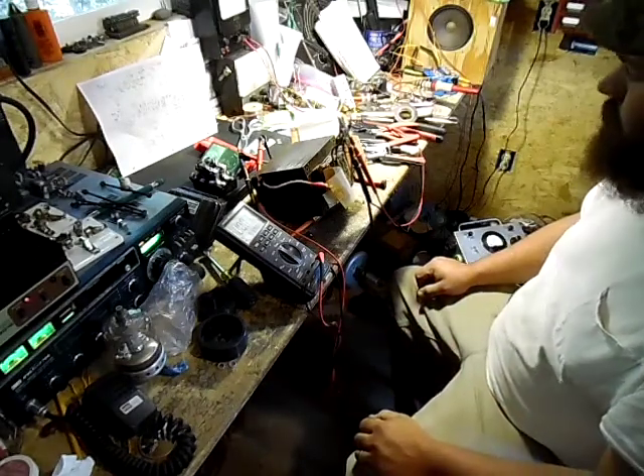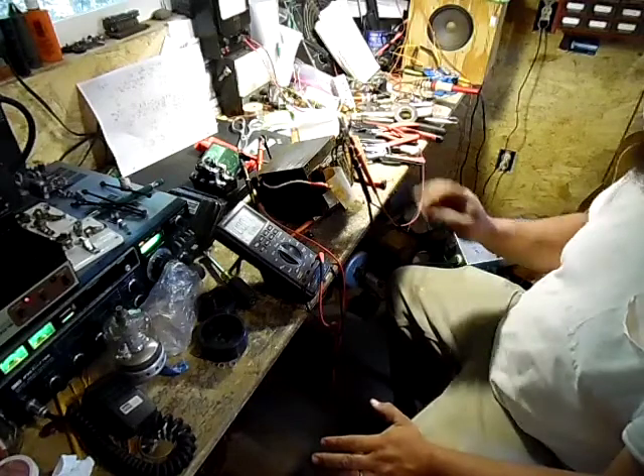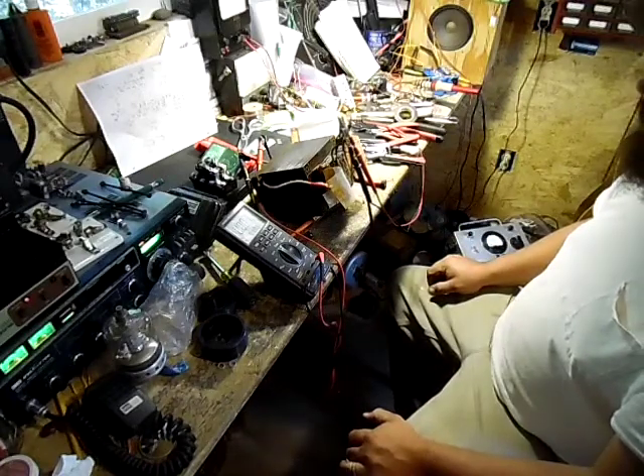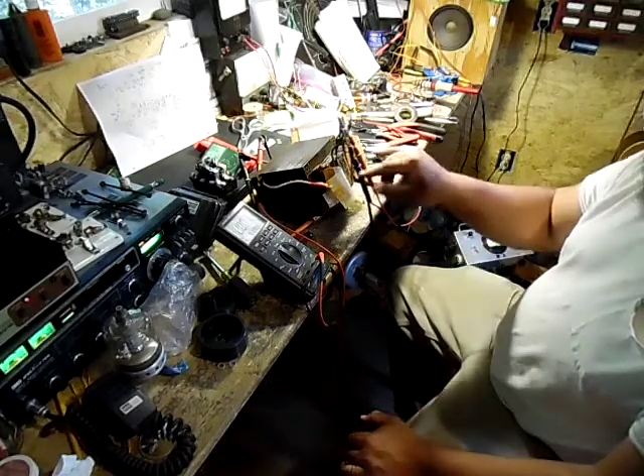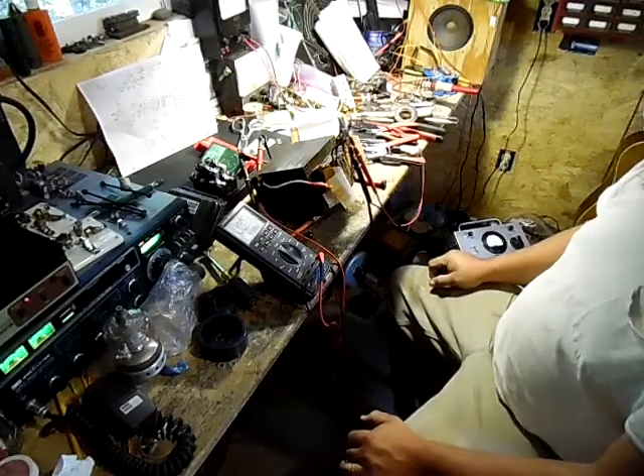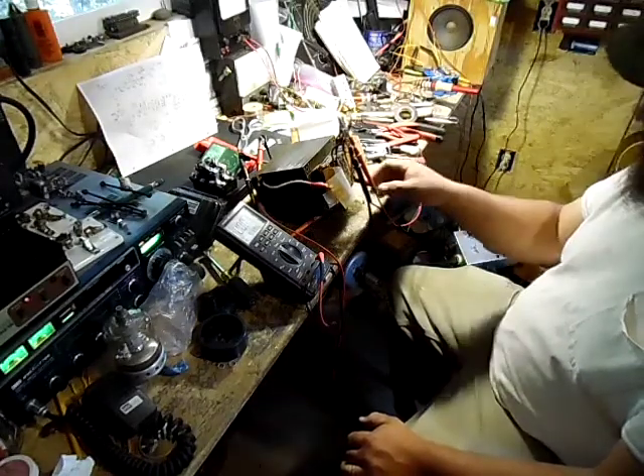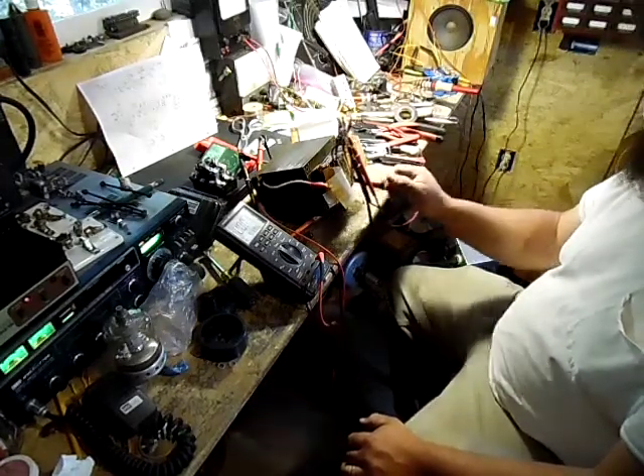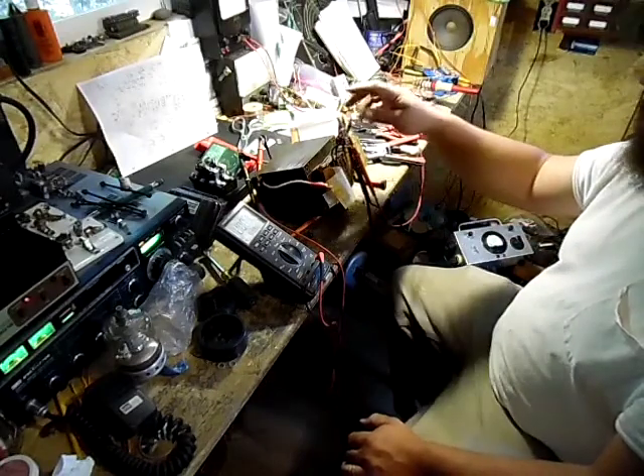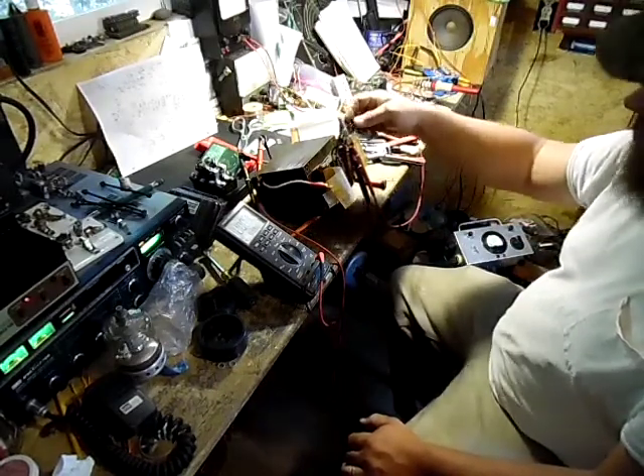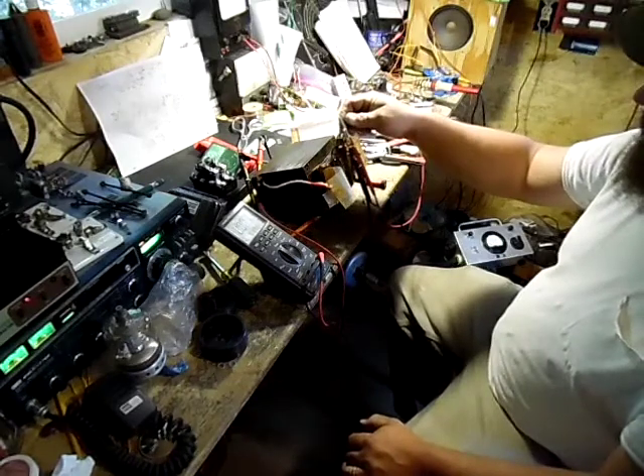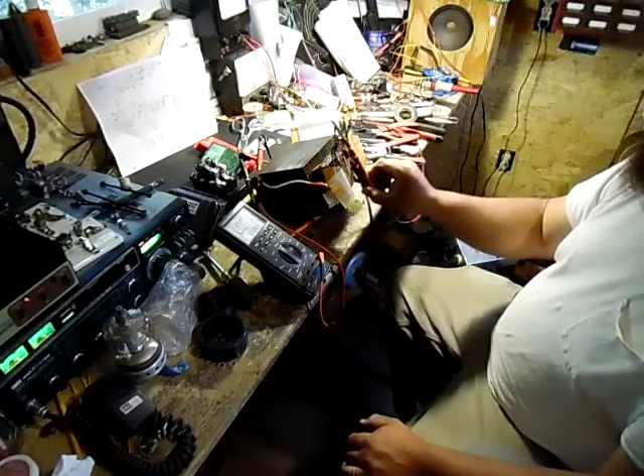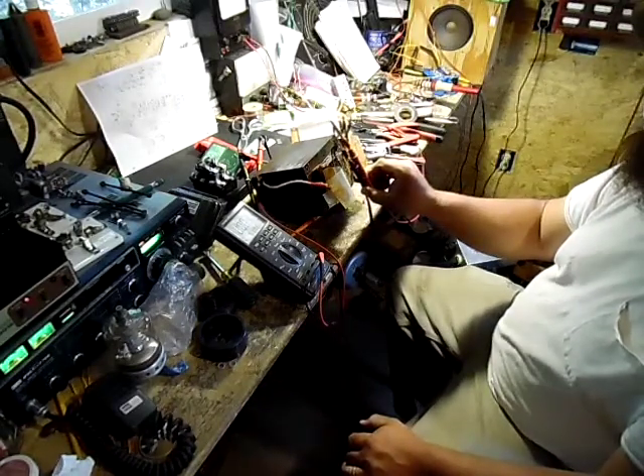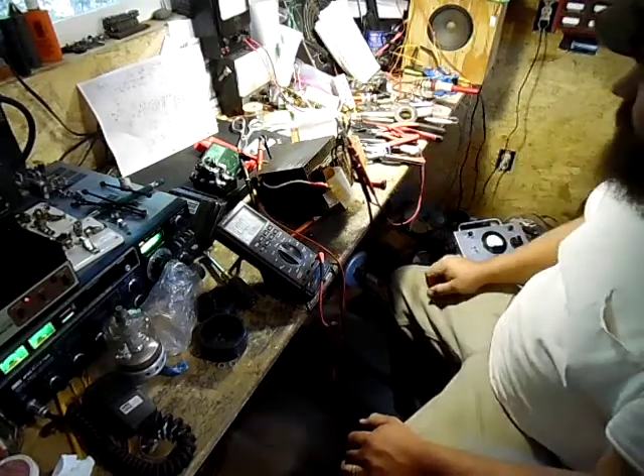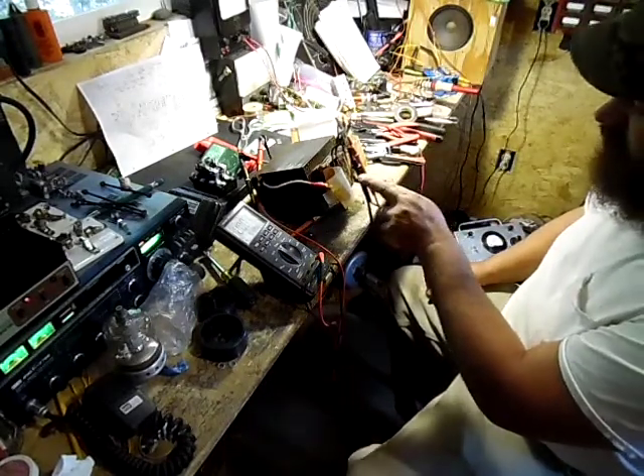And so I decided to take it apart, take it open, and see where the short was, or if it was right here where it's soldered. And it's not. It's somewhere down in the windings, and it's on this side that this is tied to. The 120 coming in is coming off of a variac down here on the floor, tied to this side. This side's got the Simpson on it, showing the shorted turn. This is the one that's shorted.